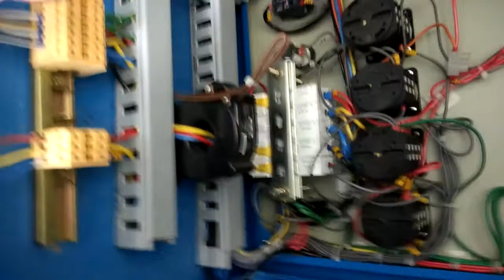म्हणजे आपलं एकच आहे ना. Our relay will take only 1 ampere maximum. So we have to just decrease the current or step down the current. My motor is taking 4.7, but my relay is taking only 1 ampere. So we will use CTs. Like the same in a differential relay, which will take only 1 ampere, and my motor is taking 5 ampere. So 5 by 1.